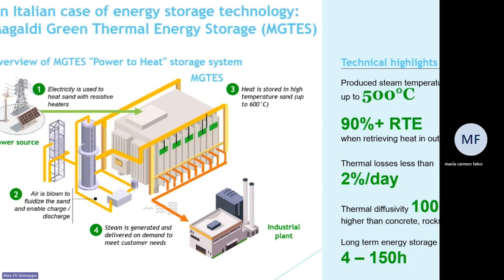The main application is power to heat, and the maximum temperature that can be reached by the sand is over 1000 degrees. But due to the materials used to produce the immersed elements like electrical resistors and also the immersed heat exchanger, the maximum temperature reachable by the sand is set to 620 degrees. And also, the thermal fluid produced can be produced in a range between 200 and 500 degrees that can be used in a large number of industrial sectors, in particular pulp and paper, food and beverage, and others.